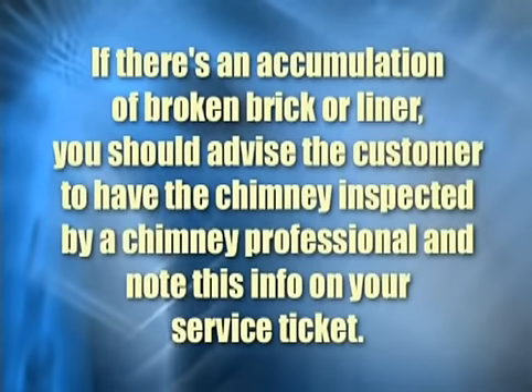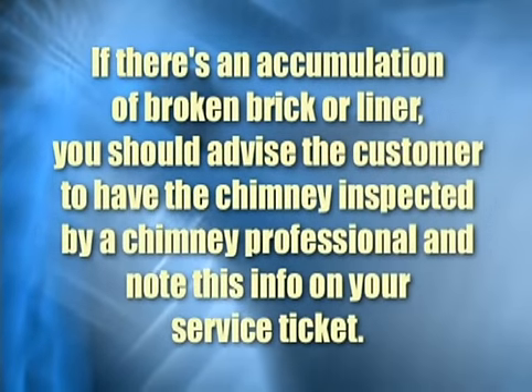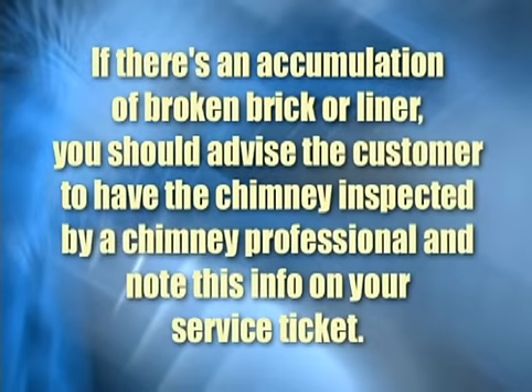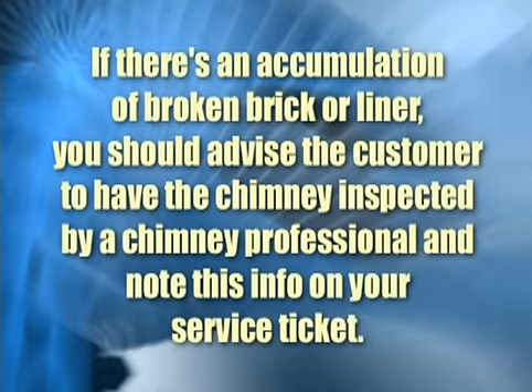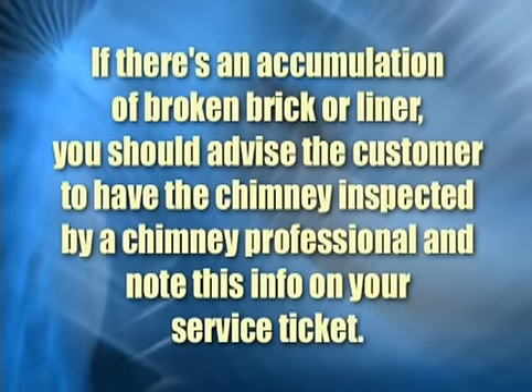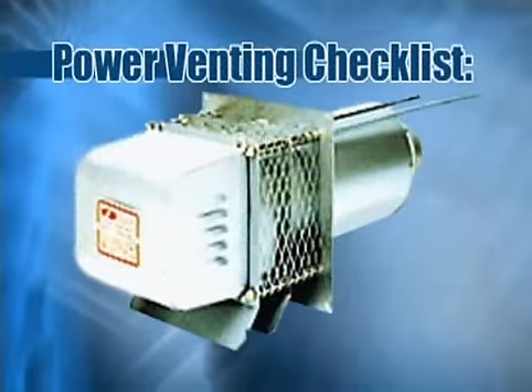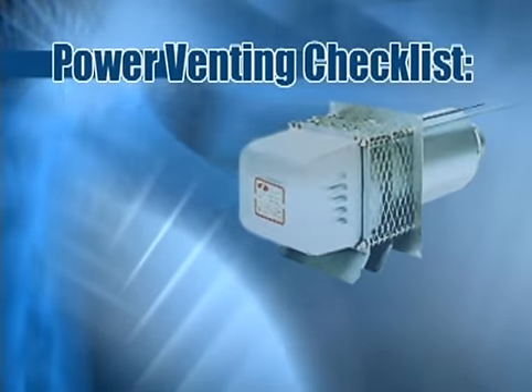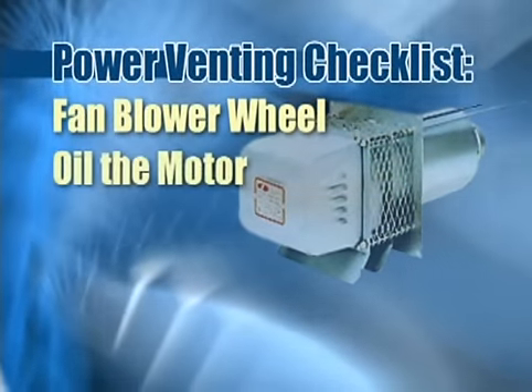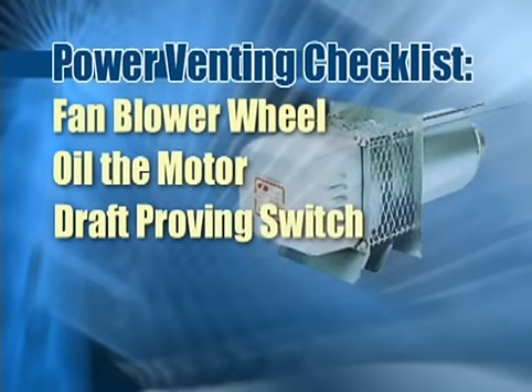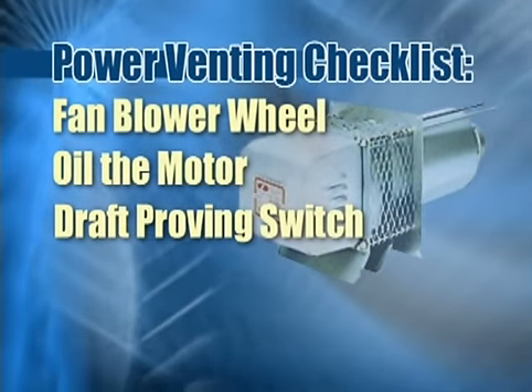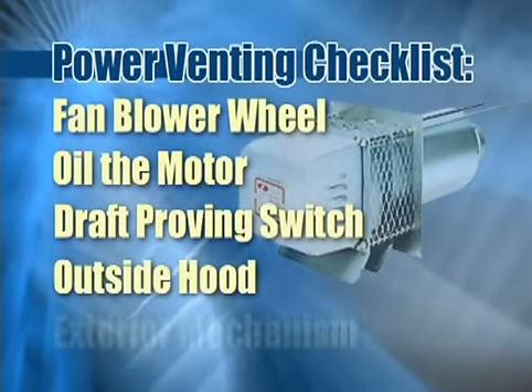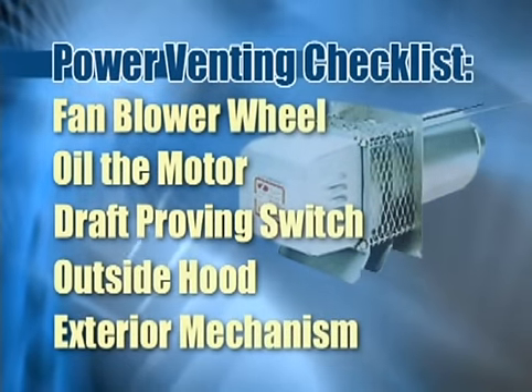If there's an accumulation of broken brick or liner, you should advise the customer to have the chimney inspected by a chimney professional and note this info on your service ticket. If the unit is equipped for power venting, clean and check the fan blower wheel, oil the motor, and check the draft proving switch. Remember to check and clean the outside hood and exterior mechanism.